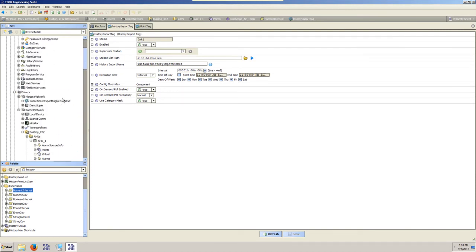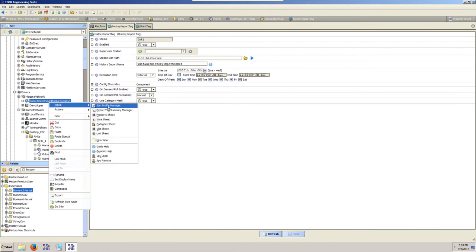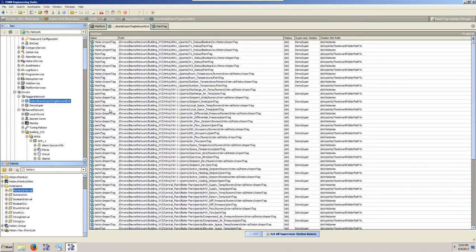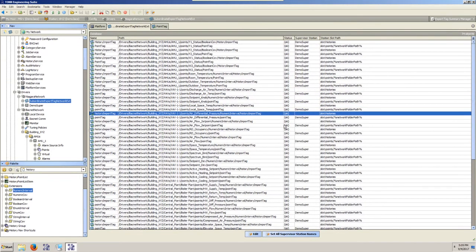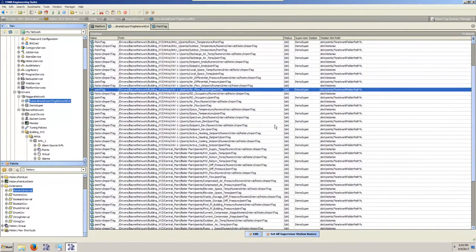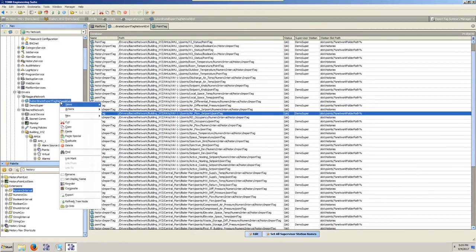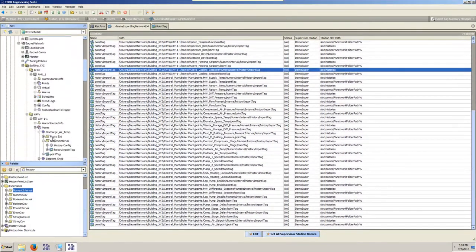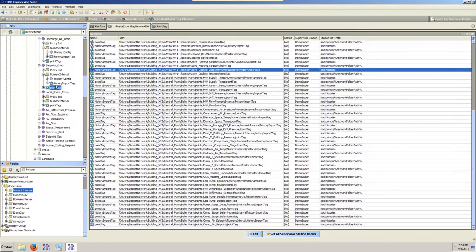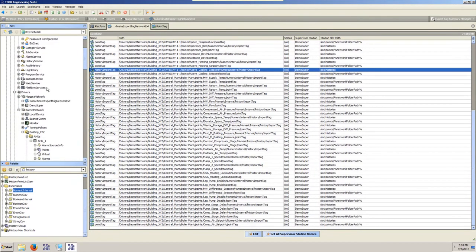So we screwed up and we forgot to set the export tag, the station name, on some of these. So some of these, when we join, it's either going to fail or it's not going to pass them on up because we didn't tell it where we want to send them. When you look at the tags and that export tag summary manager that brings you to this screen, there's a button here to just say, hey, set all my tags to go to XYZ station. So if you do forget it, there's a quick, easy way to set it on everything. So now we're set. We got the history tags. We got point tags on all our other devices. We're ready to join this up.